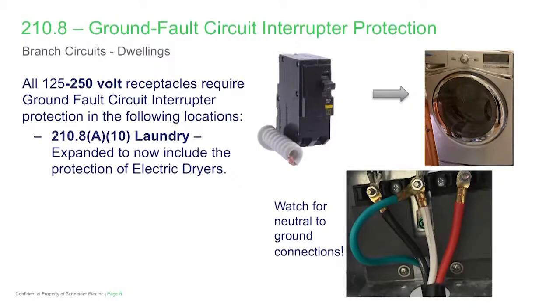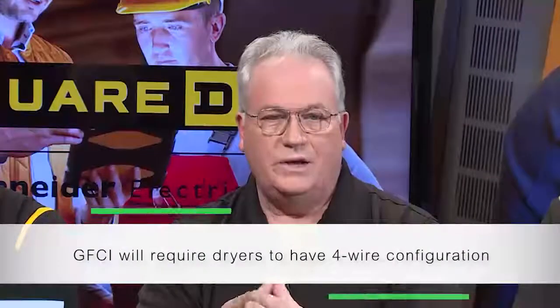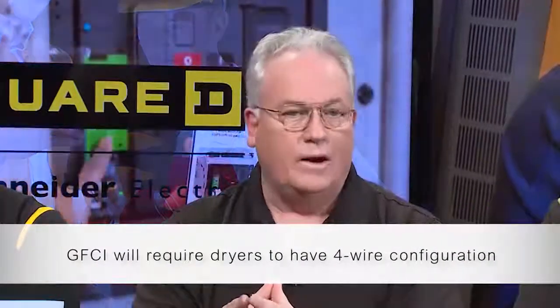Something to really watch for: GFCI kind of acts like a policing agent if you get a neutral-to-ground connection downstream of a service main bonding jumper. When appliances like dryers are sold at a retail outlet, they're typically sold without a cord. The cord can be purchased in a 3-wire or 4-wire configuration, but those appliances typically come with a neutral bonding strap already installed. So installers or owners are going to have to pay attention to that — if there's a GFCI ahead of that circuit, it's certainly going to let you know it's not wired correctly.